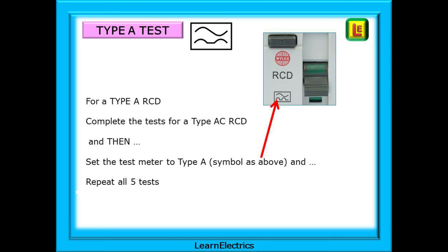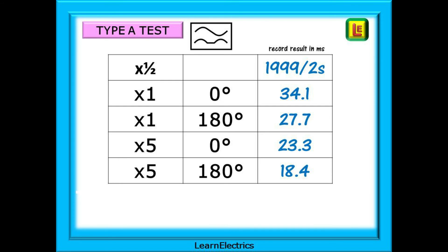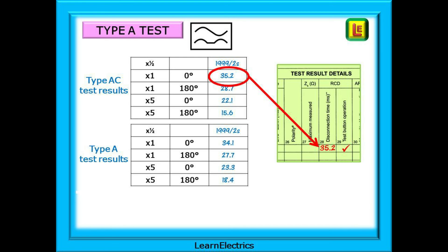To test a type A RCD you will complete 10 tests in total. Complete the five tests exactly as for a type AC RCD, and then set the test meter to type A and repeat all five tests on this A setting, making a note of the results as you go. You should now have two sets of test results for the one type A RCD — a set of type AC results and a set of type A results. Now choose the worst case results — the highest readings — for the schedule of test results, and remember to press the T or test button.